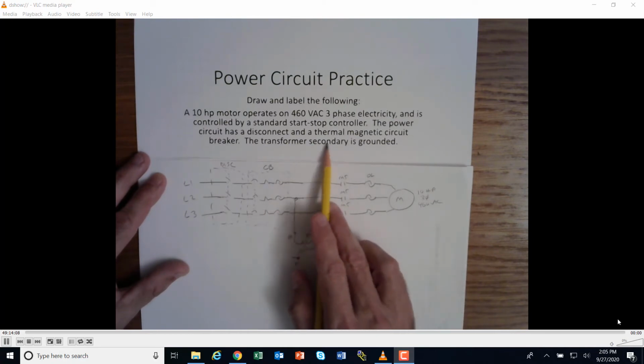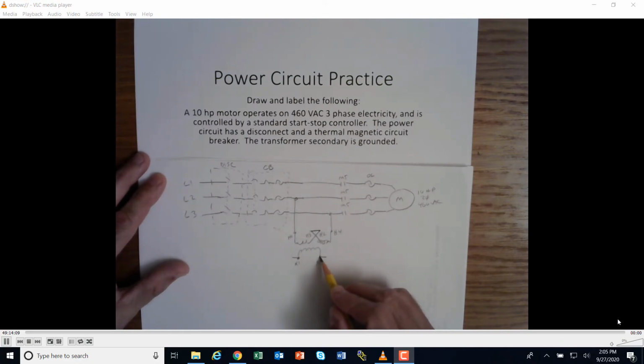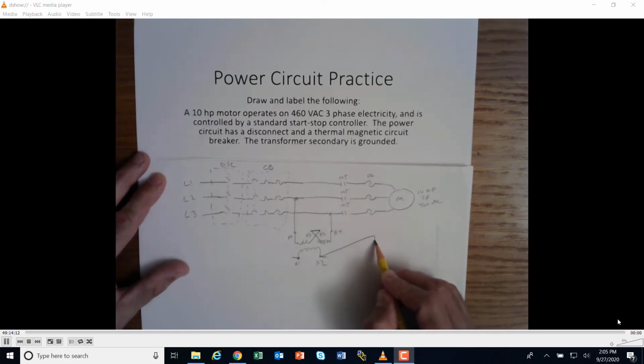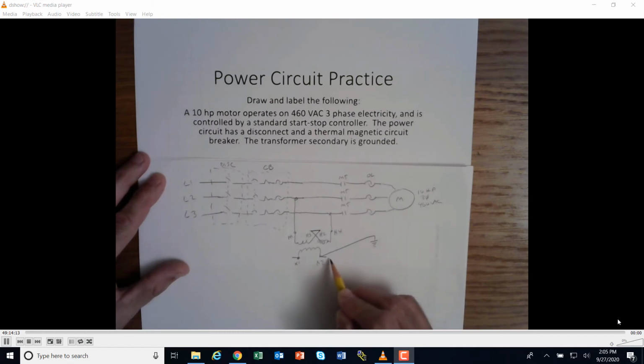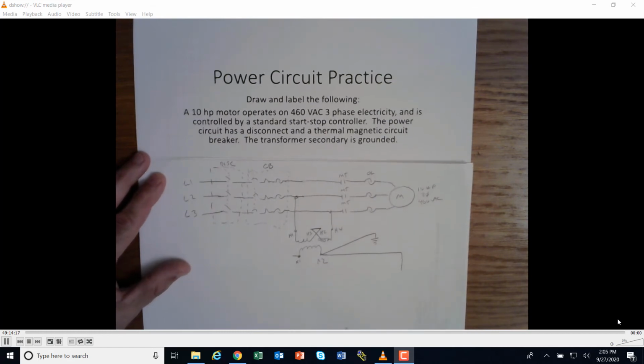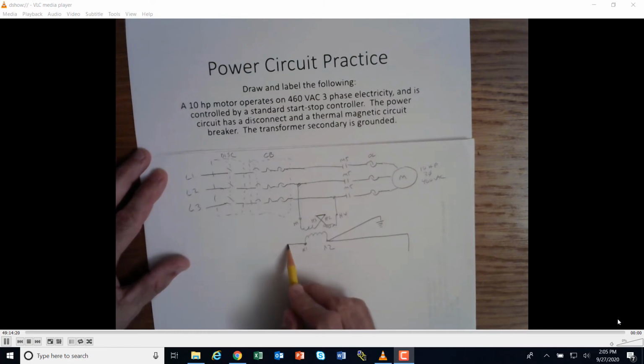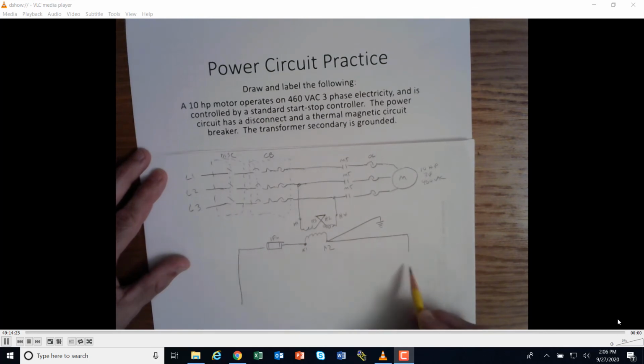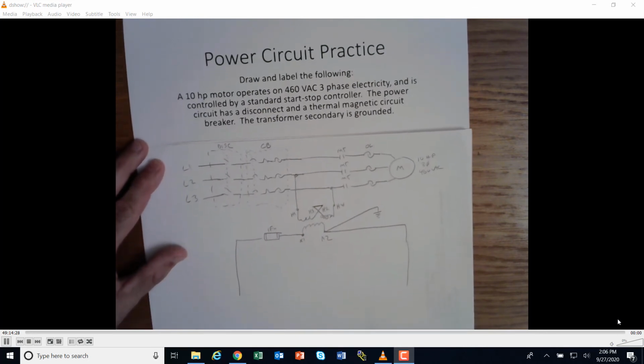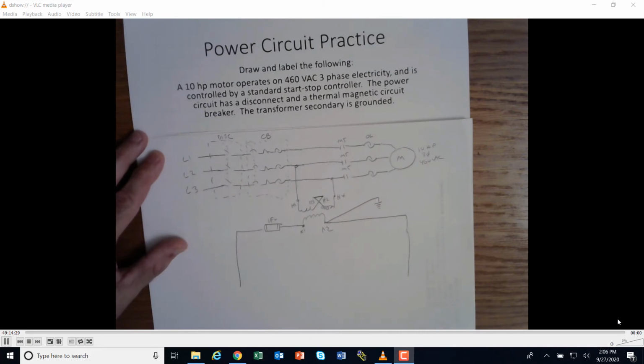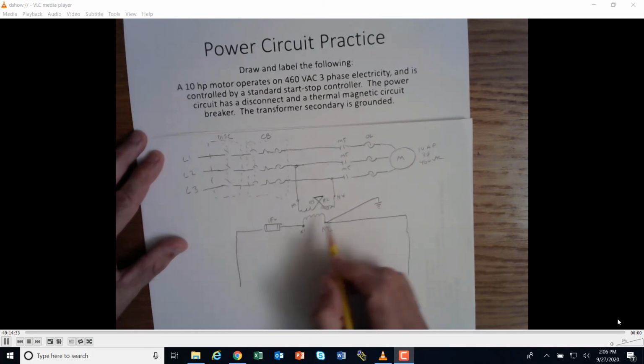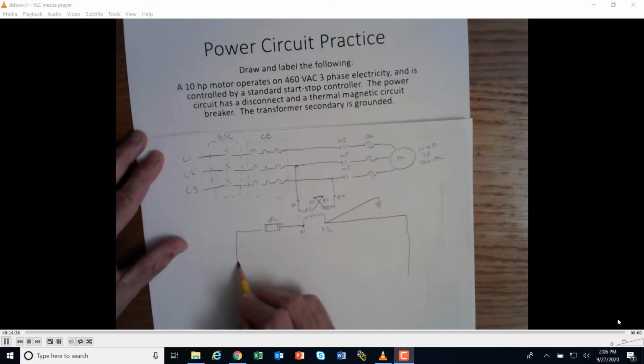It says the transformer secondary is grounded. So this right here is grounded. That means that we do not need a fuse on this side of the transformer, the neutral side, but we're going to go ahead and we're going to put one right here. Okay. And then there's my rails for my control circuit. So it's basically a start-stop, we're going to put an overload in there.